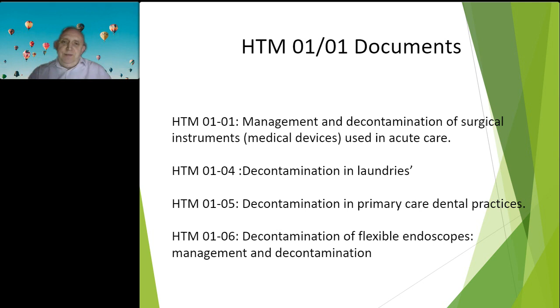So HTM 0101 is segregated into 5 sections. Part D is dedicated to the washer disinfectors themselves. Very much based upon new guidance, looking at the prion protein risk. It goes into residual proteins, how we monitor residual proteins. One thing I'm particularly keen on: it's okay monitoring protein left on devices, but we need to clean. We need to make sure that protein does not adhere to the instruments. And part of that is effective cleaning.